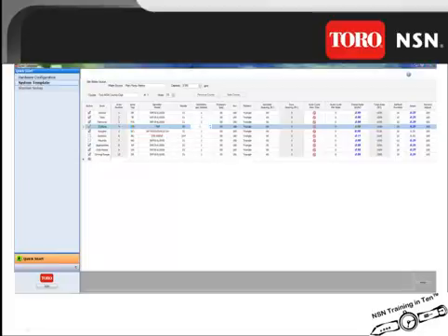Now select the number of sprinklers per station that is the majority in that area-based program. The next column allows you to set the pilot valve pressure for the majority of the stations. There are 4 choices in the pressure settings: 50, 65, 80, or 100.